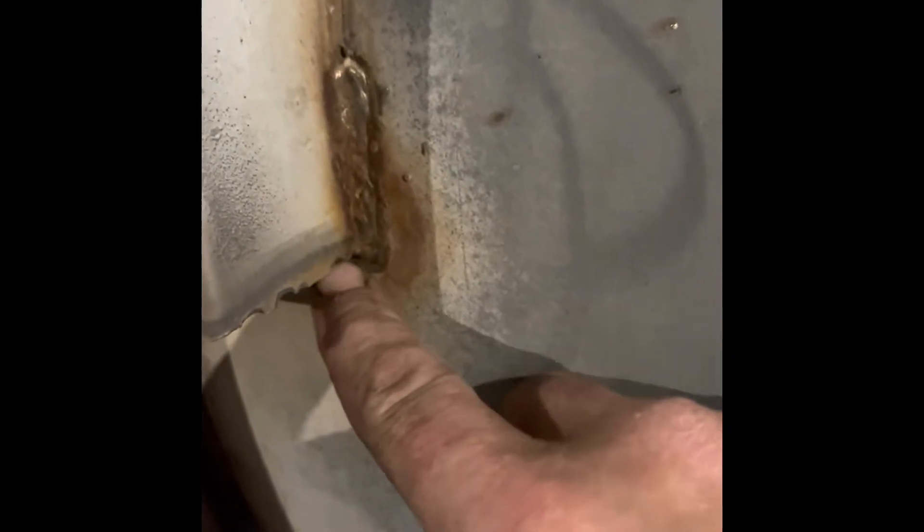Okay, is that focusing? Yeah, so we've got a crack there — that's nothing too major. There's that crack there — that's more structural. I also had staining around here, and I can see where it ran down there. That running down is water running down — yellow stains from this tube of the heat exchanger. See if I can catch it on camera for you. You can see it if you know what you're looking for — it's all rusted through right there. I mean, it's a wonderful little mess.